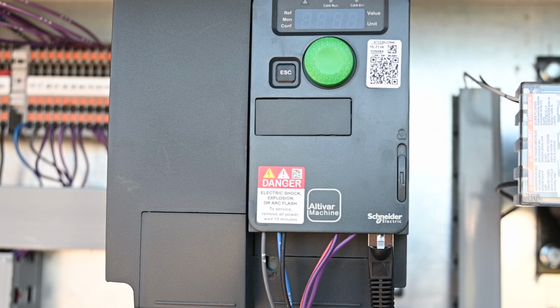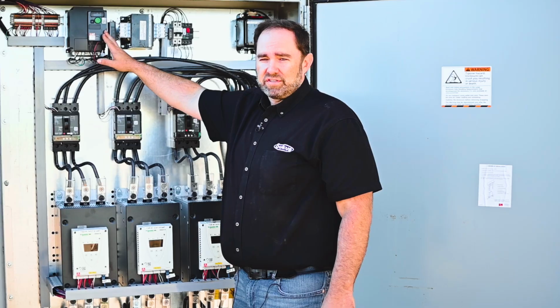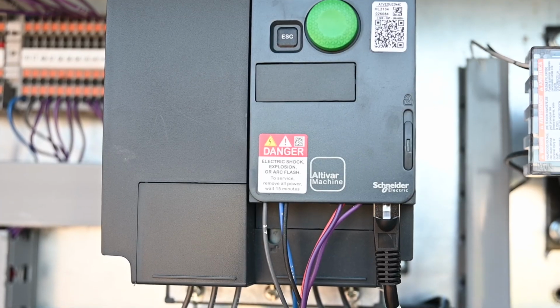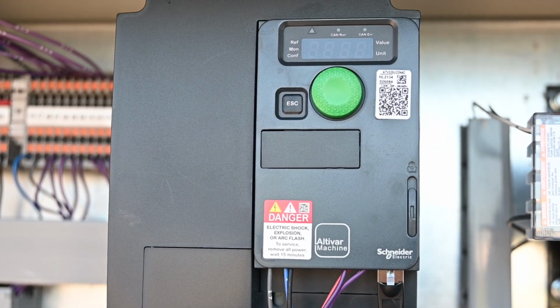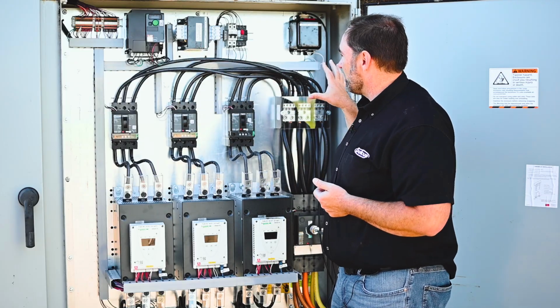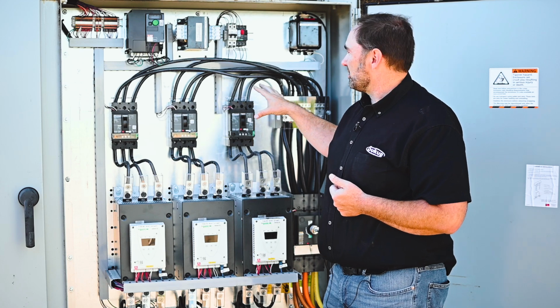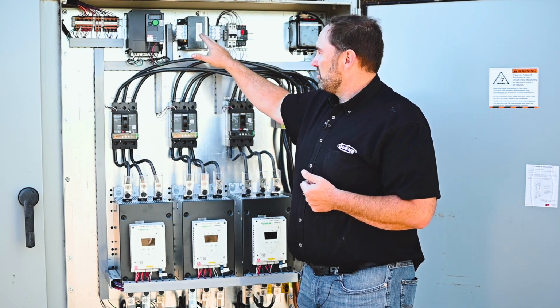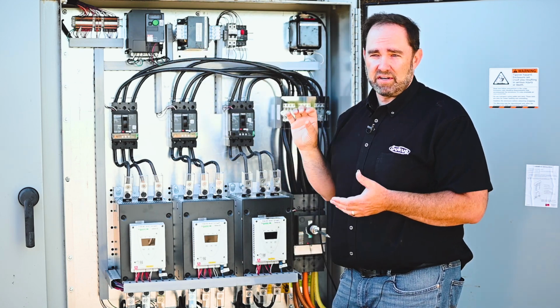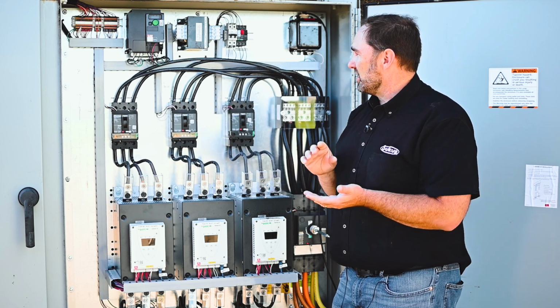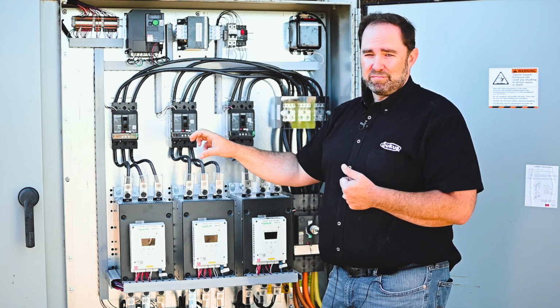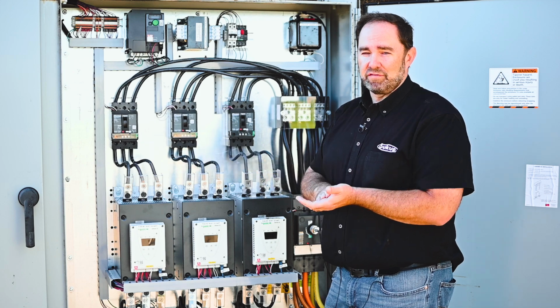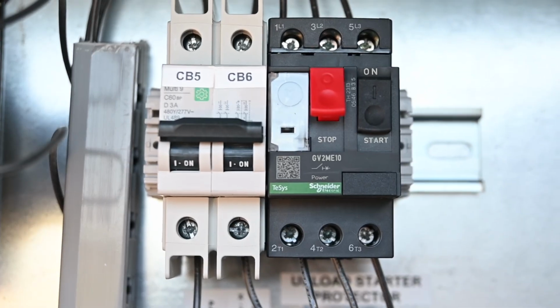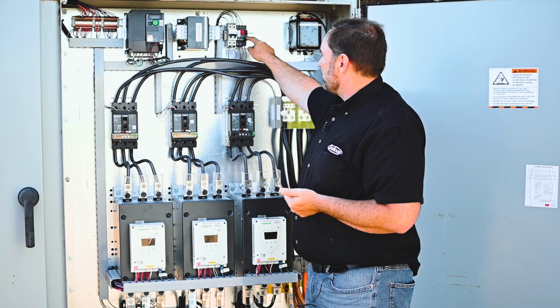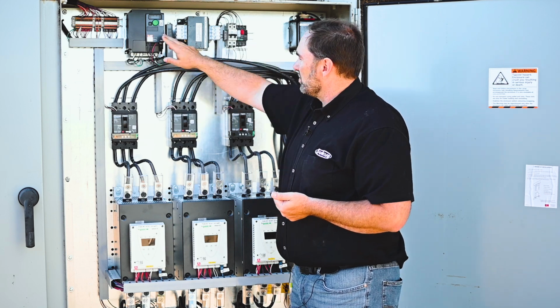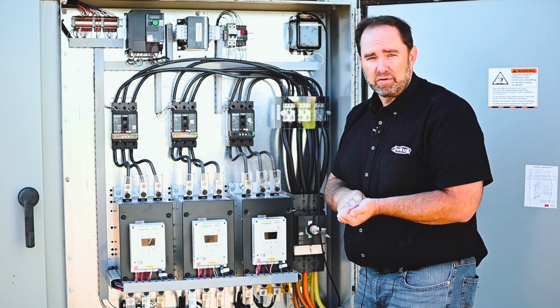Up here on top, we have the VFD. This is for the unload rotor, so this gives a variable speed to the unload rotor, controlling the rate of discharge of the dryer. This is the control transformer, so this is going to take our high voltage, in this case 480 volt, and knock it down to 110. And then we use 110 volts for a lot of the things on the pipe train that we talked about. That's also what gives power to the power supply that reduces 110 to 24 volts for control power. There is a circuit breaker here on the primary side of the transformer, and then we have an overload here that is actually for the VFD for the unload. And those are the components on the right-hand side.